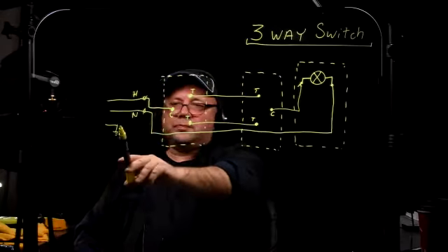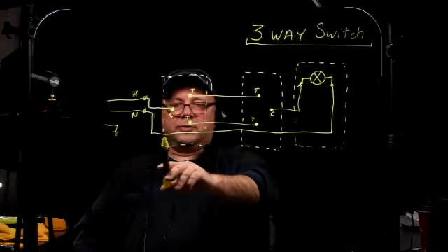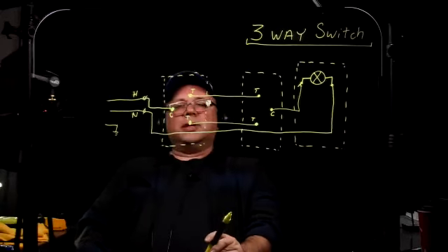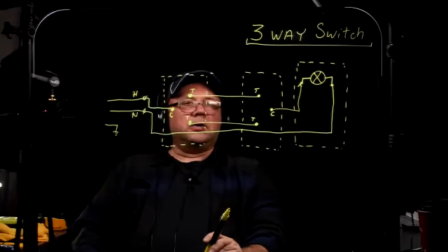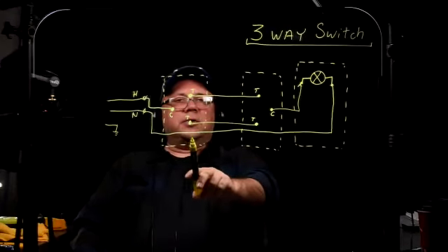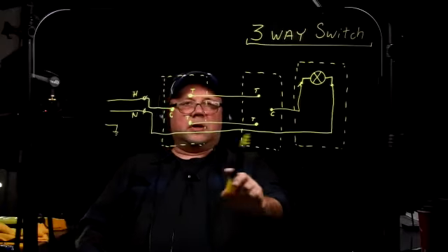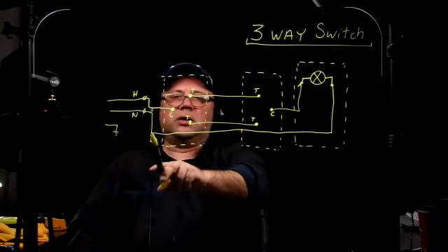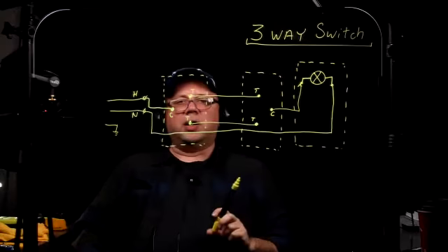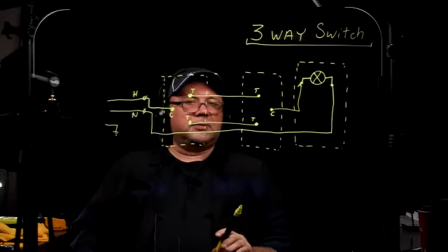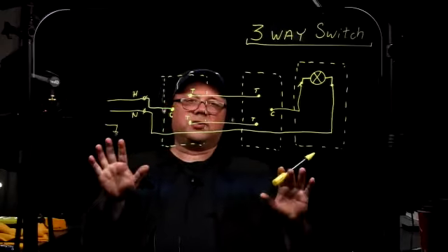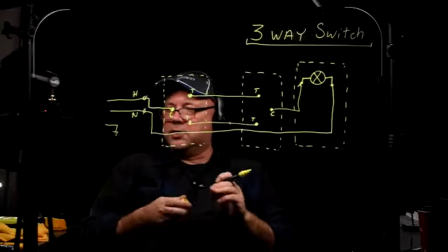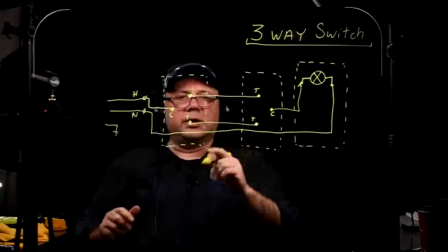Of course, the ground or bonding wire is going to have to make its way also to at least the first box, and if we're dealing with EMT, electrical metallic tubing or conduit, then the grounding or bonding is going to be carried through the metal part of the conduit. If we have PVC conduit, then we're going to have to install another wire that goes all the way to the last box, because the PVC doesn't conduct electricity, so we have to supply the other. But just for the sake of clarity, we're going to leave that out for now and concentrate on the electric current passages.